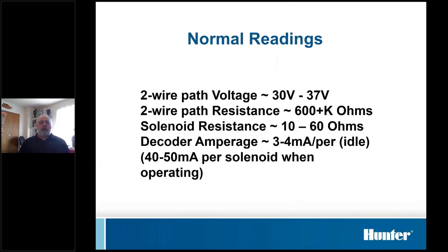So just some of the normal readings that you'd see. The two-wire path voltage, you need to know your meter, 30 to 37 volts. There's a fair amount of variance. If I hook my meter up to a two-wire path, the voltage will be bouncing between high teens and something around 40 volts. It is what it is. As long as you know what your meter reads it as, you know what's right and wrong.